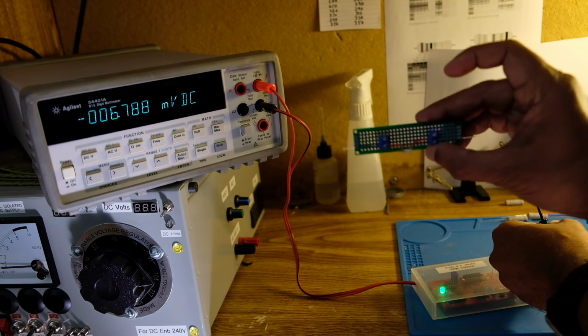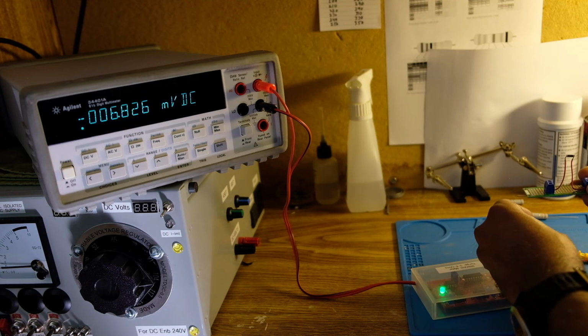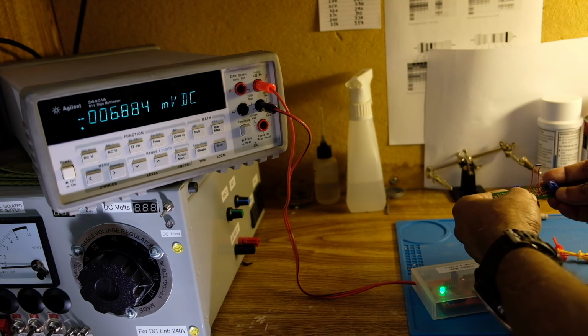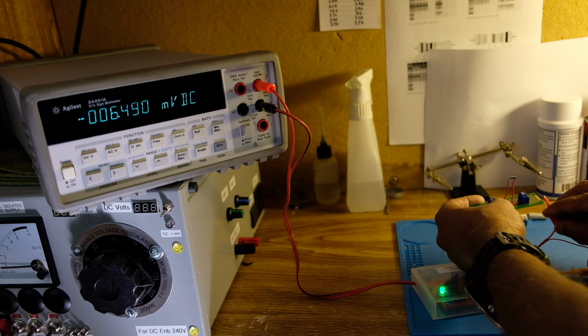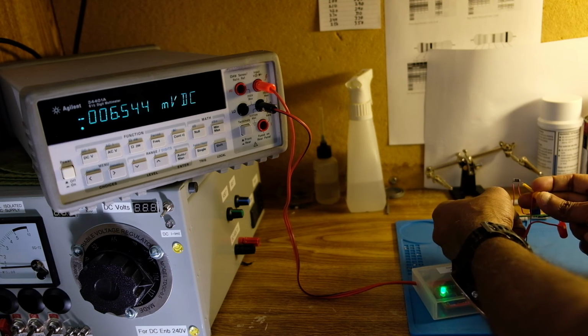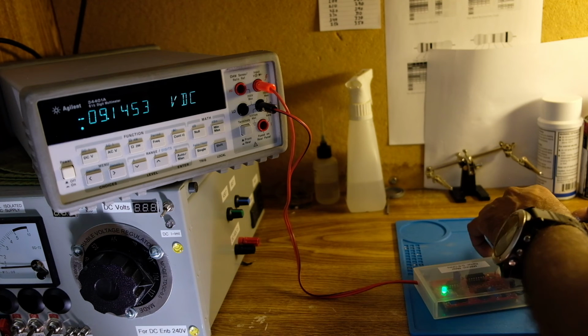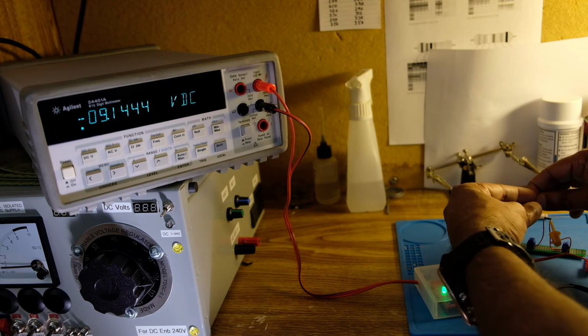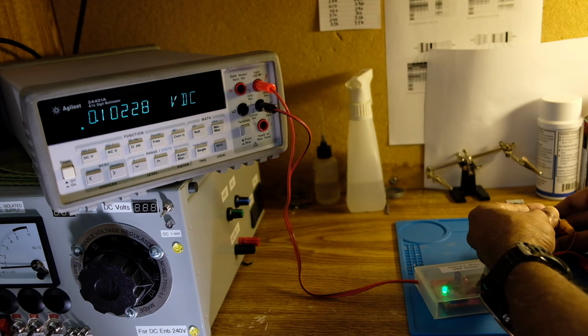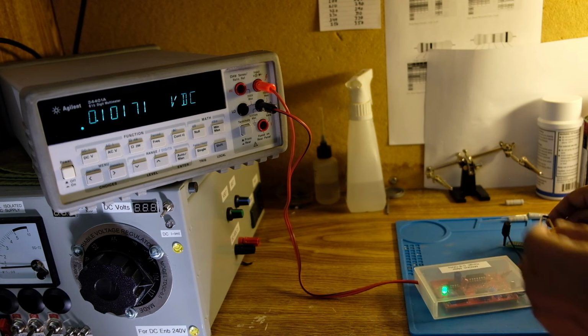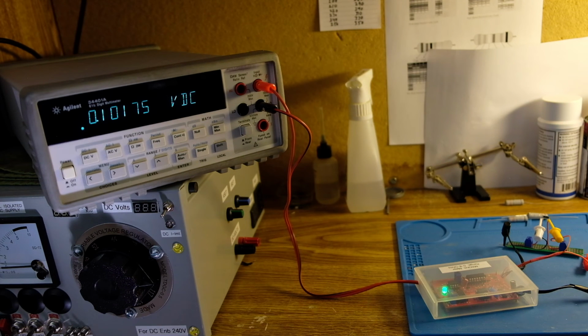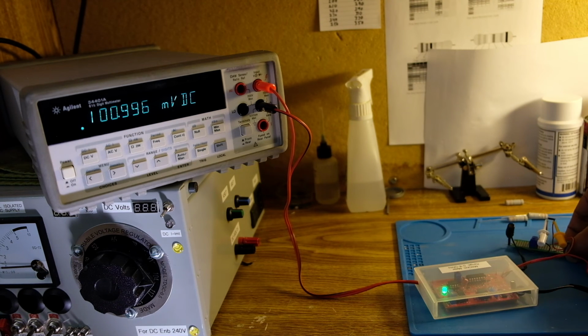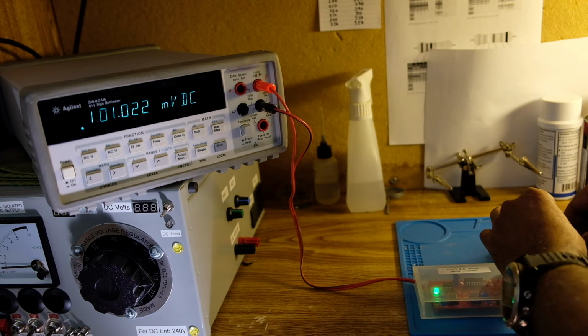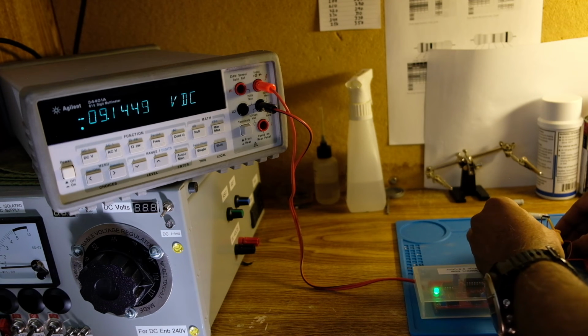Now this is a 0.1 ohm resistor. It's going to have more self-heating, but if you do a quick measurement it's probably okay. So there you get 0.10175. As you can see, the meter is accurate—I'll have to confirm that—but it's got high resolution, at least for now, and it can distinguish down to hundreds of micro-ohms or even smaller.